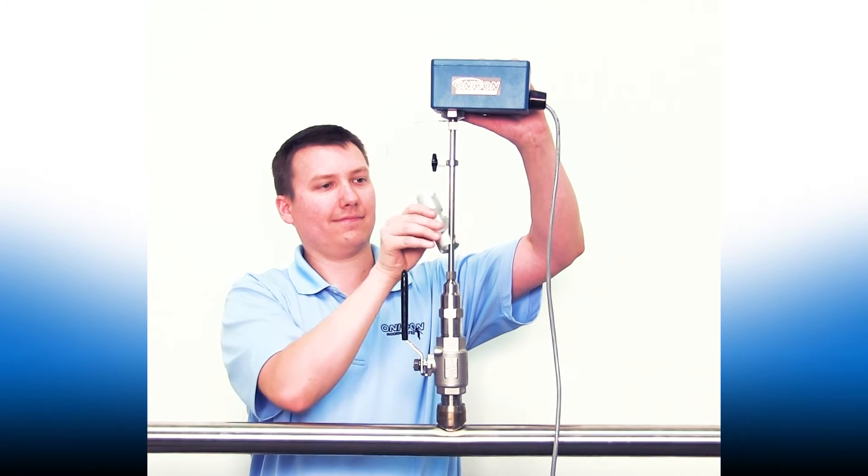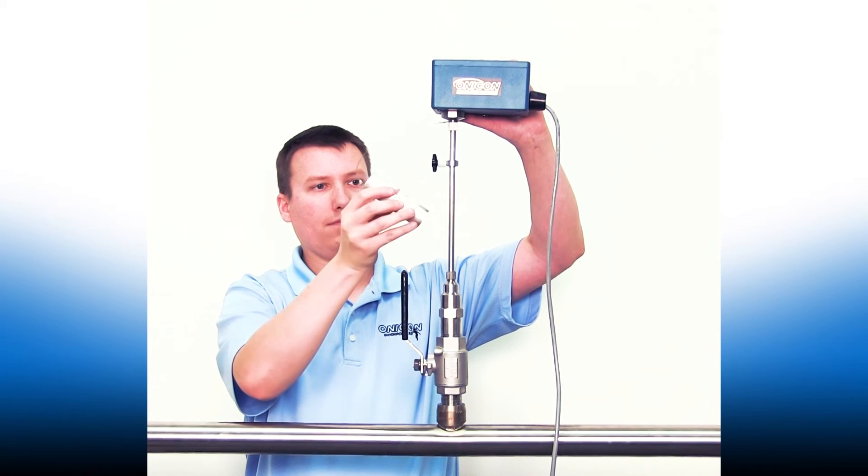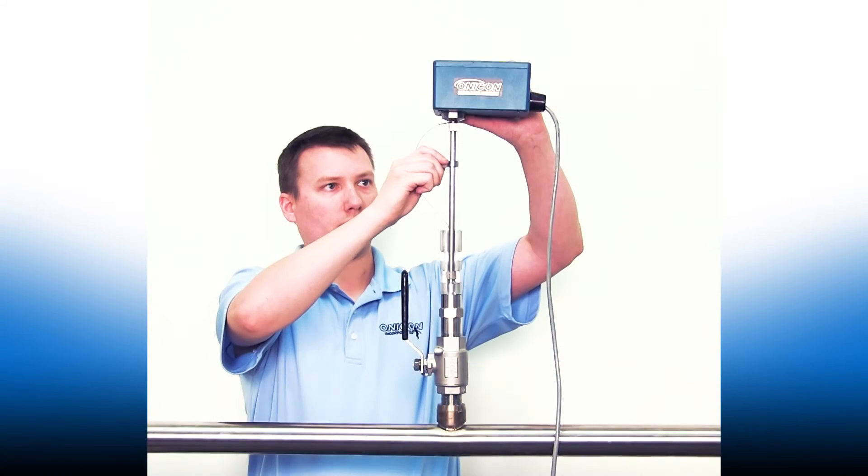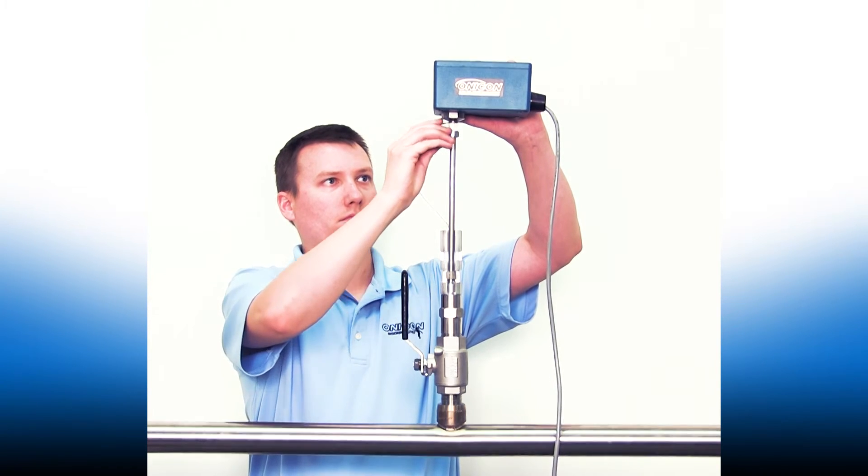Place the insertion depth and alignment tool around the stem, making sure that the beveled edge of the tool is flush with the beveled edge of the hot tap adapter. Loosen the collar and slide it to the top of the stem and lightly tighten it.